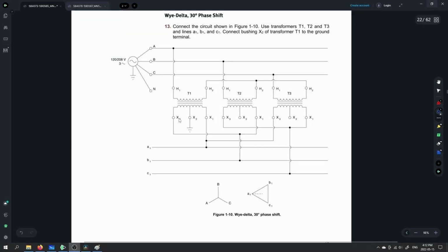All right, guys, next one is the Y to delta. We've got the 30-degree phase shift now because we're going from one configuration to another. So Y to delta 30-degree phase shift. That means that our primary is being connected up as a Y. So you can see here that all of the H2s are tied together here. That means that we're going to have 208 volts between any of our lines up here. Right, so 208 between these guys, 208 between these guys, and obviously 208 between the A and the C. Those guys are now feeding each of our transformers, but H2 is tied together there.